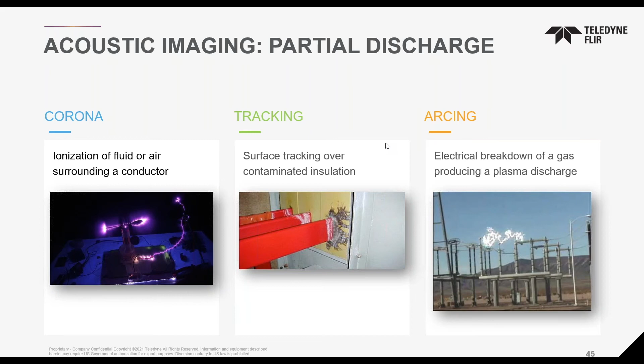Here are some real images. This is a faulty insulator, and the camera gives you diagnostics as you take the image, actually classifying what's going on, such as a discharge on the surface or inside that component.